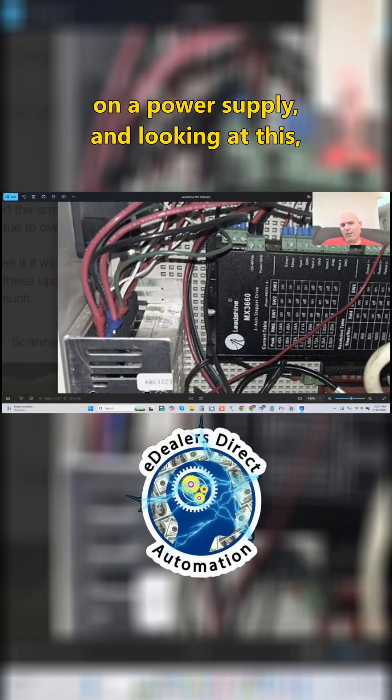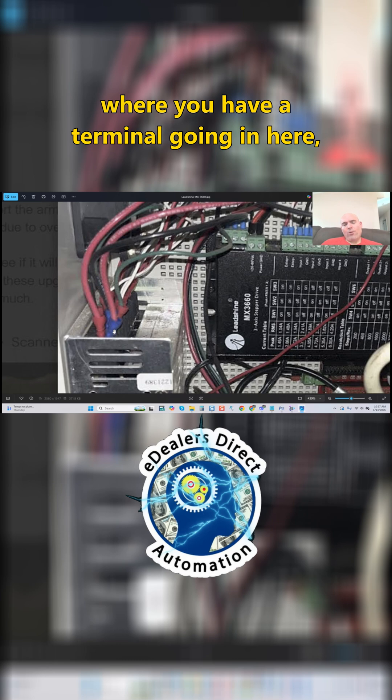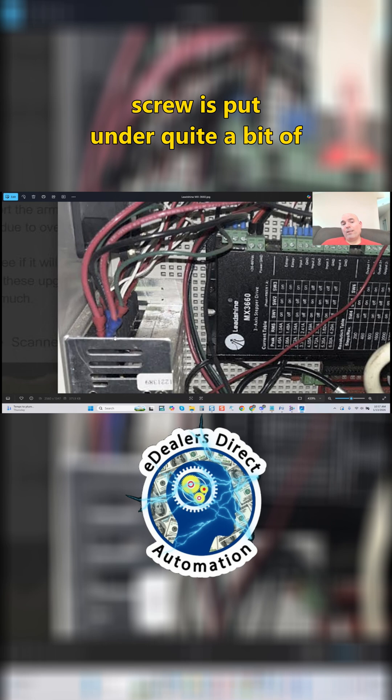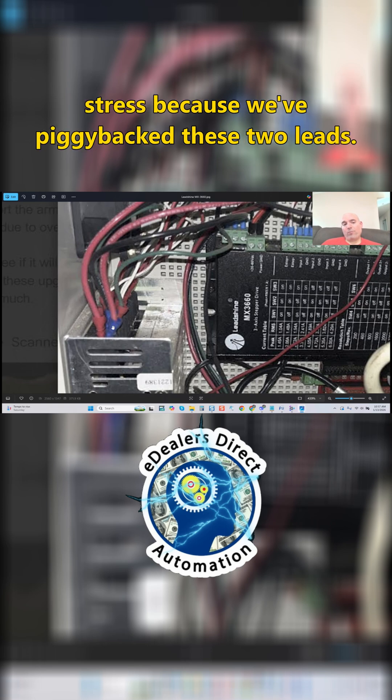Looking at this, where you have a terminal going in here with typically one screw—that screw is put under quite a bit of stress because we've piggybacked these two leads.